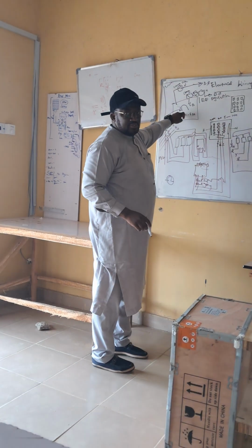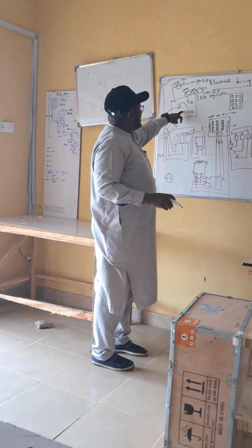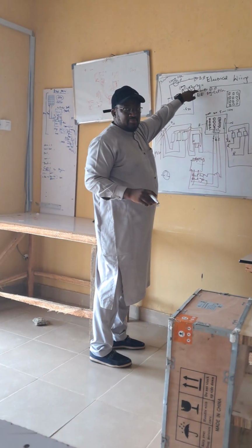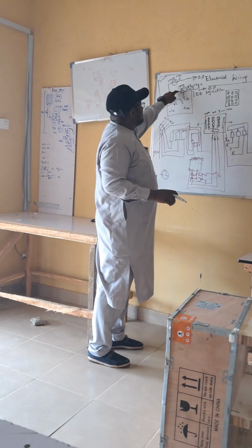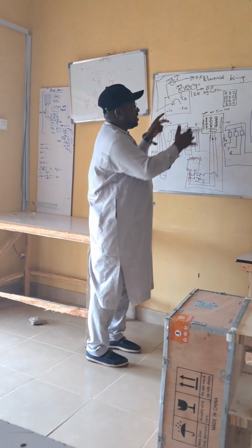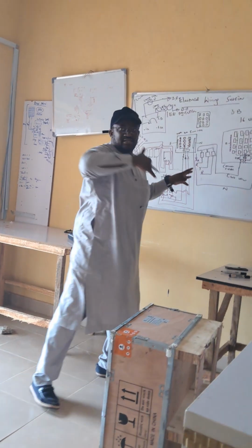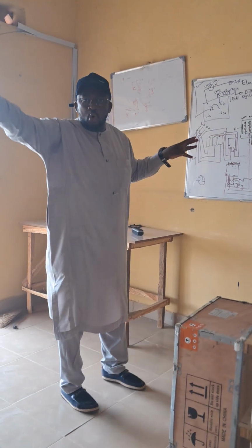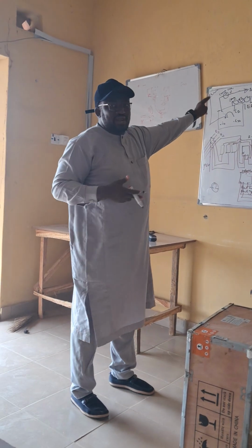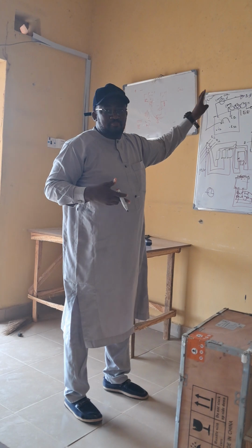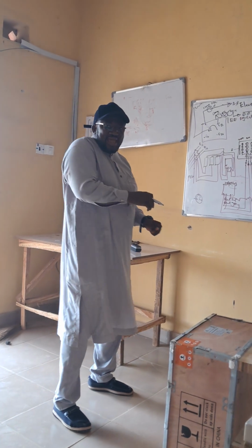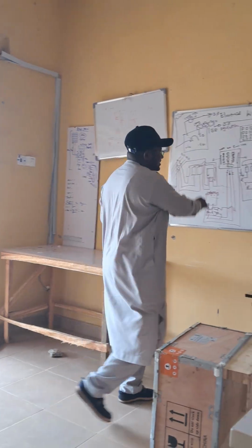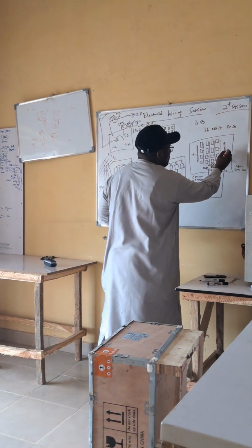This is our switch. If we are using two gang, this is the first lamp and this is the second lamp. Okay? So this is one bracket. Let's say you have 1, 2 here and the third one is there, which means you have 3 bulbs. So all of them will be connected together, just like this, to serve as parallel connection. Their end terminal, which is neutral, will move straight to this distribution board terminal of N.